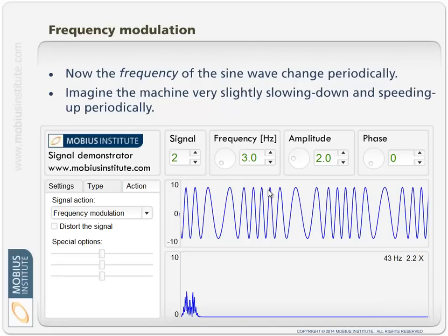So we get this variation in speed, which is therefore variation in the frequency. It's a periodic motion as each tooth comes into mesh, and we can see therefore a variation. We can see it occurring more so at some points in the rotation than at other points, and therefore once per revolution the machine can appear to change speed. Either way, even though this looks quite strange down here, we see lots of sidebands.